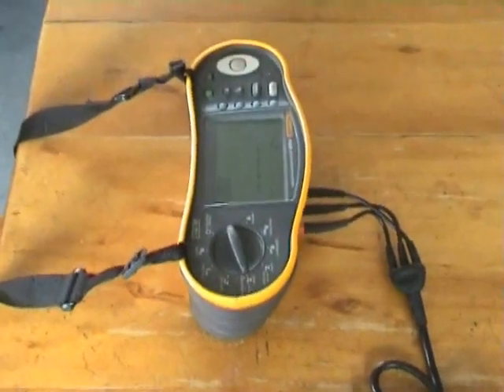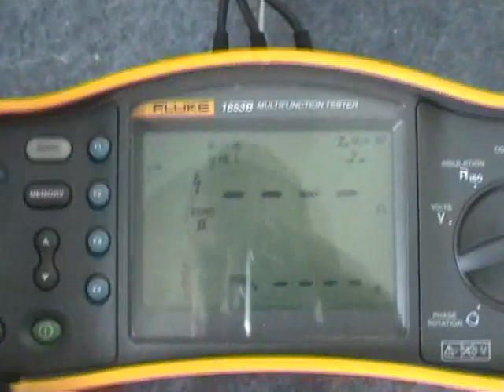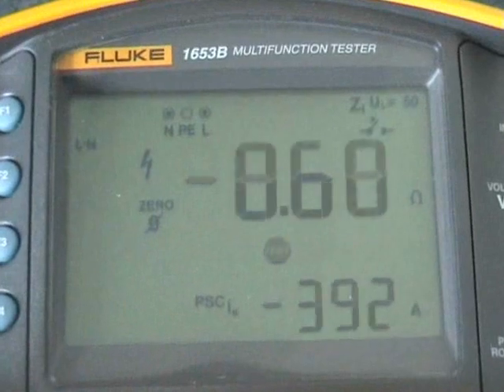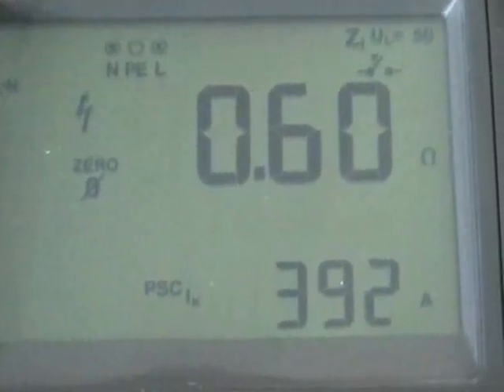Okay, let's take this one in the kitchen. The reading is 0.6 ohm, 392 amperes available. It's not a bad power point.